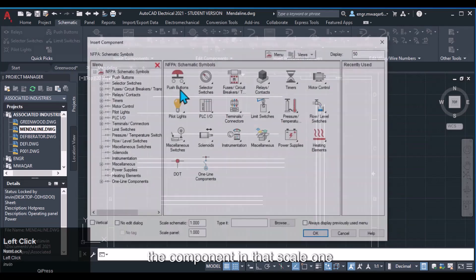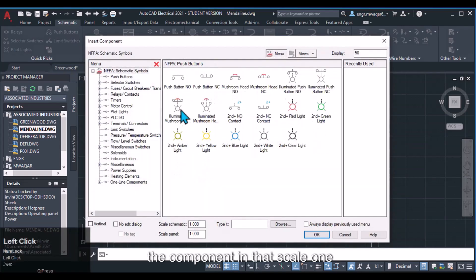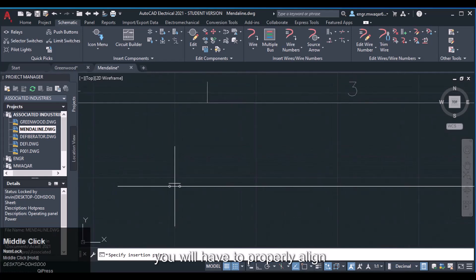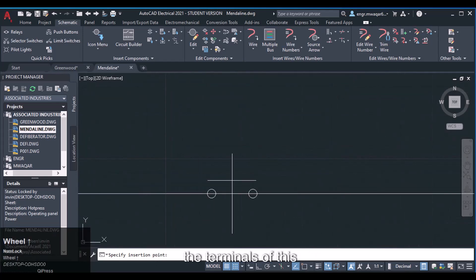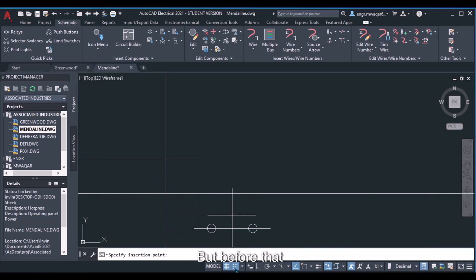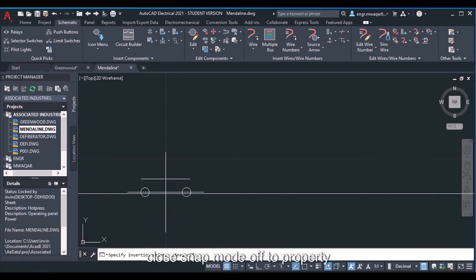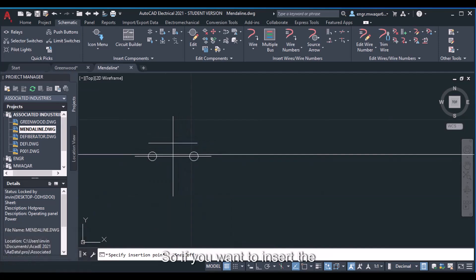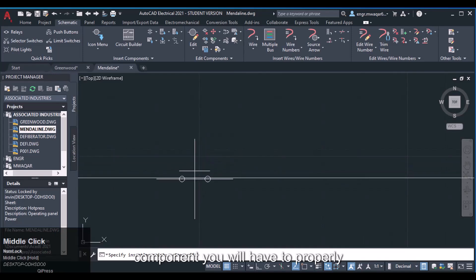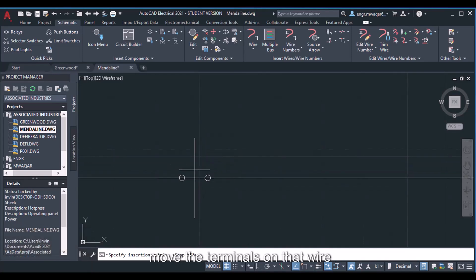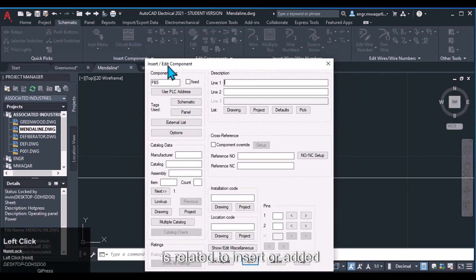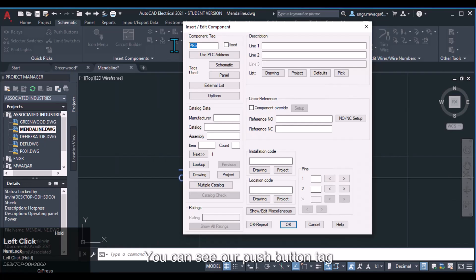Let's insert a component at scale 1. To insert a push button, you need to properly align the terminals of the component on the wire. Turn snap mode off to properly align the terminals, then click once to place it. A dialog box appears for inserting or editing the component, and you can see the push button tag is automatically assigned — for example, PB5.